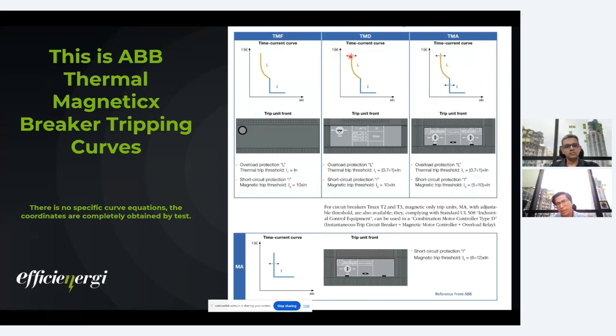Again, this region in particular is covering the overload protection requirements. As the name suggests, thermal depends completely on the bimetallic characteristics of the tripping element that has been used in the breaker. Then this one is magnetic tripping. Magnetic tripping is completely based on a magnetic plunger that picks up the energizing quantity, and generally it trips in 10 to 20 milliseconds.